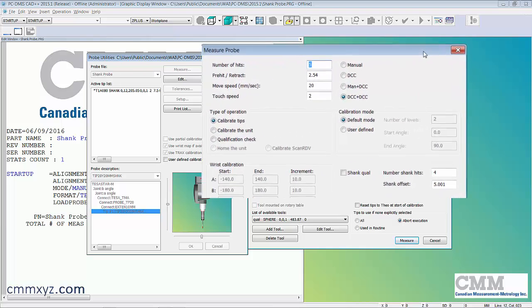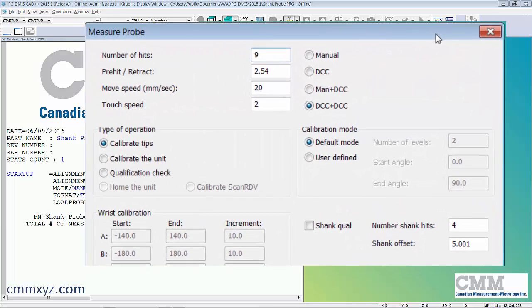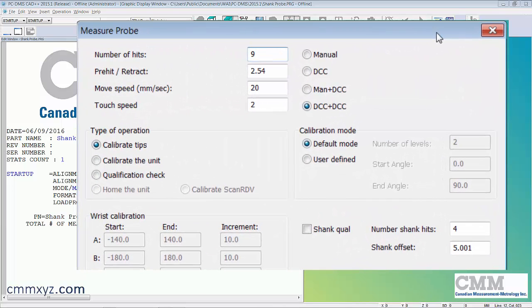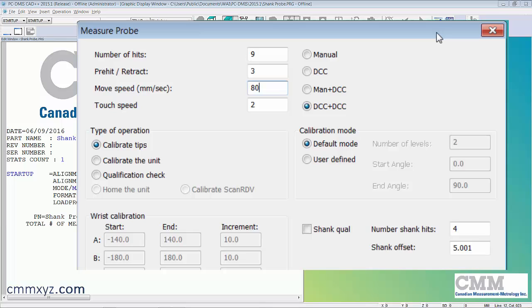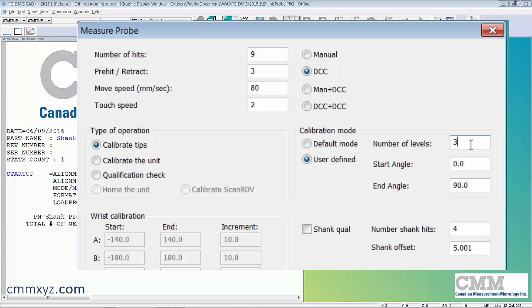I'll set the number of hits to nine, pre-hit retract to three millimeters, move speed to around 80 millimeters per second, touch speed at two. I'll go with DCC mode only, user defined. I'll split those nine hits up into three levels starting at the equator zero and the end angle 90, the north pole.